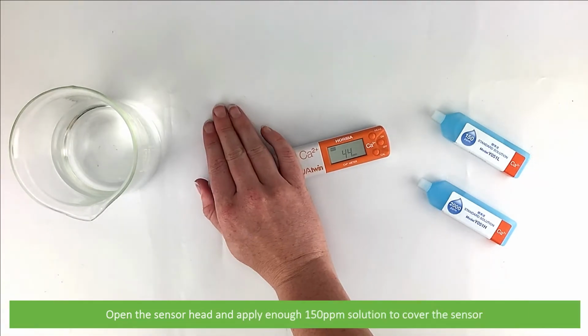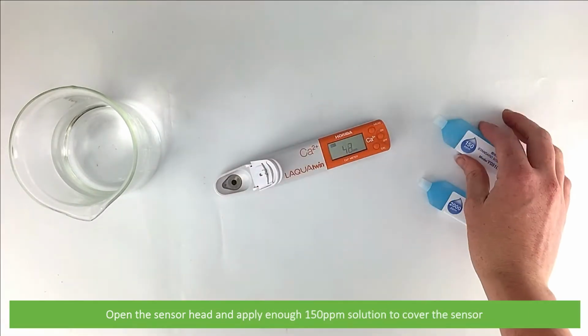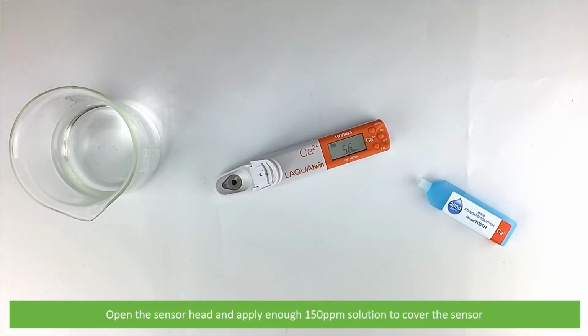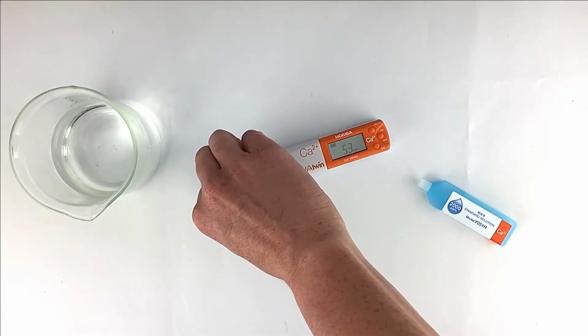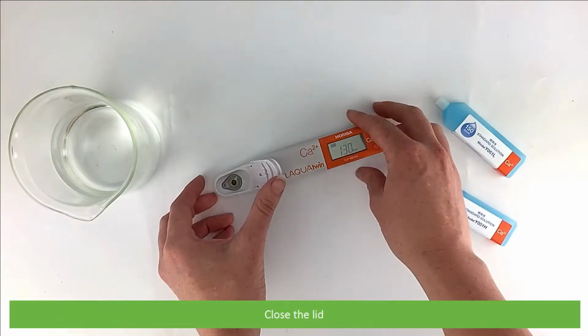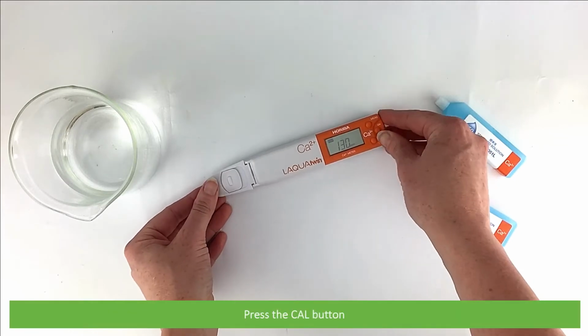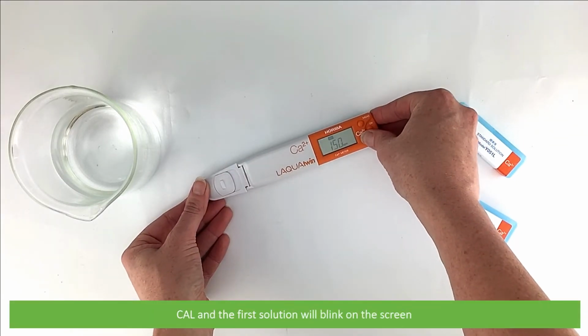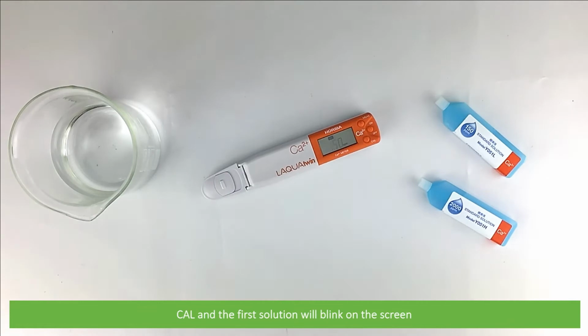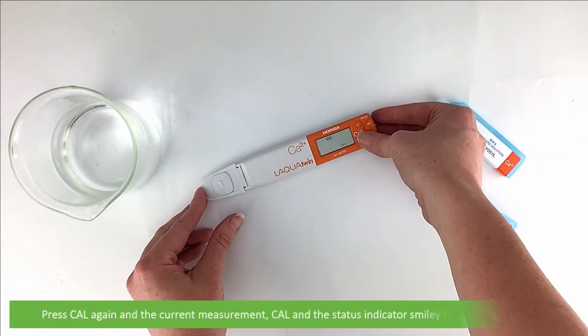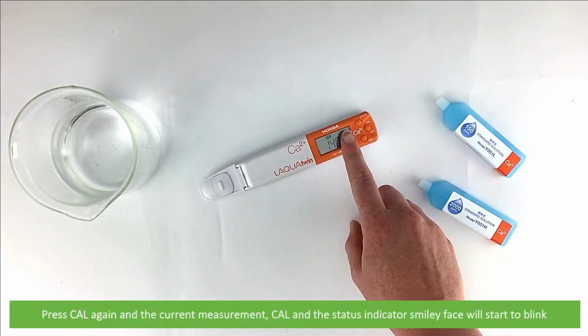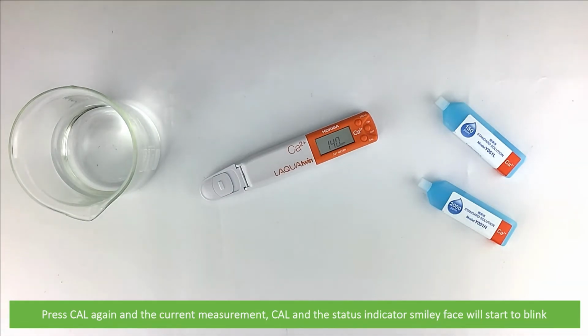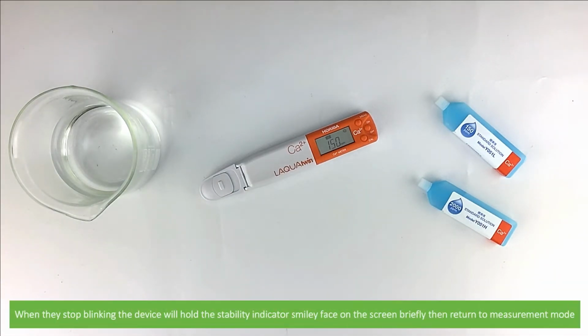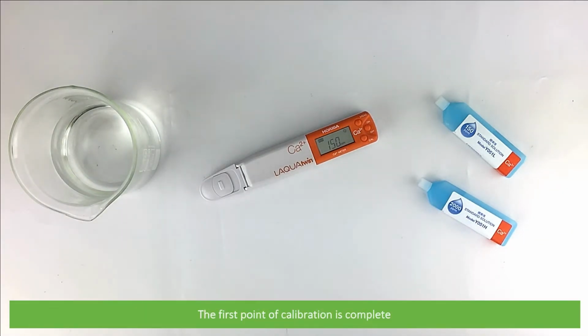Open the sensor head and apply enough 150 parts per million solution to cover the sensor. Close the lid. Press the Cal button. Cal and the first solution will blink on the screen. Press Cal again and the current measurement, Cal, and the status indicator smiley face will start to blink. Once these stop blinking, the device will hold the stability indicator face on the screen briefly, then return to measurement mode. The first point of calibration is complete.